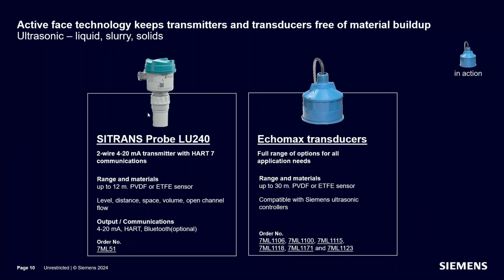This can be a little confusing because it's actually an ultrasonic transducer, but it has a 4 to 20 transmitter on top of it, so it is an analog output. If you wanted to utilize this in an LT500, you'd want to purchase the LT500 with the analog input. Again, this is one that would actually be configured at the LT500 rather than on a push button display on top of the transmitter.